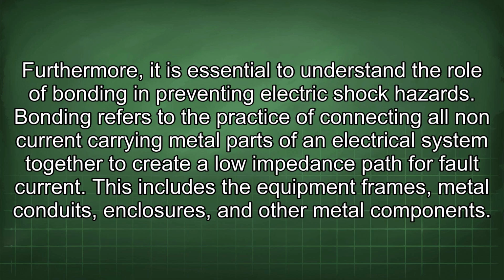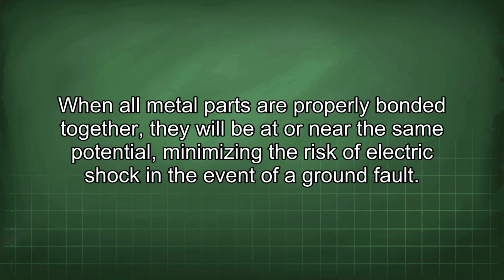Furthermore, it is essential to understand the role of bonding in preventing electric shock hazards. Bonding refers to the practice of connecting all non-current carrying metal parts of an electrical system together to create a low impedance path for fault current. This includes the equipment frames, metal conduits, enclosures, and other metal components. When all metal parts are properly bonded together, they will be at or near the same potential, minimizing the risk of electric shock in the event of a ground fault.